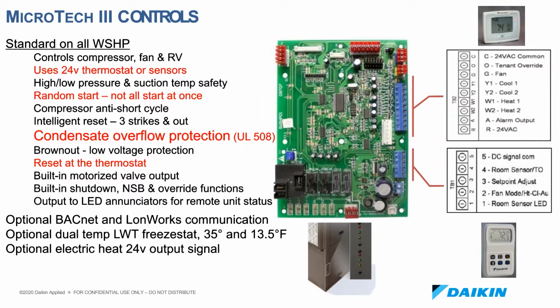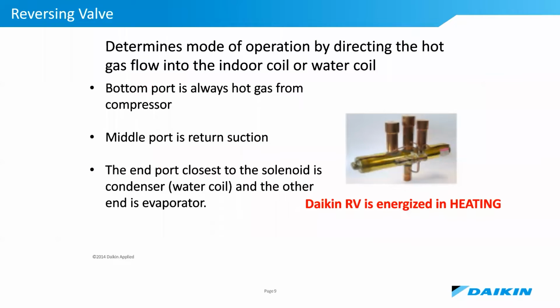It basically controls the heat pump operation from either a conventional wall thermostat or a space sensor. It includes built-in time delays and safety circuits to protect the compressor from failure. And one thing of note is that all of our water source heat pump units include a condensate overflow sensor as standard. Also, all of our units include a reversing valve as standard. One thing of note is our reversing valves are energized internally on a call for heating.